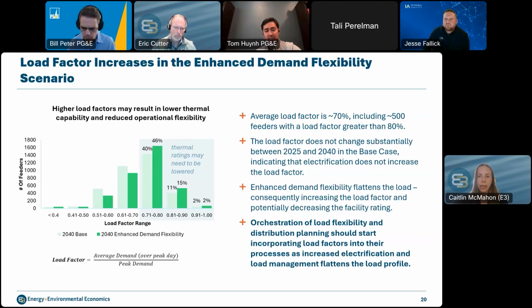The 2040 enhanced demand flexibility scenario results are in the darker green bars, and the 2040 base scenario are in the light green. And as you can see, in the range above 70% load factor, so the far right of this chart, that's the range where thermal ratings on the equipment may need to be adjusted down.